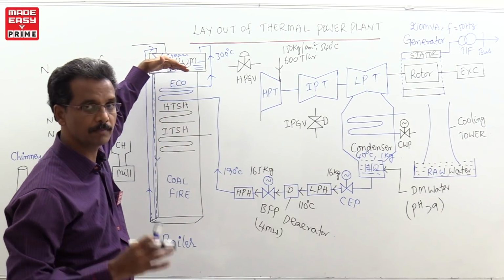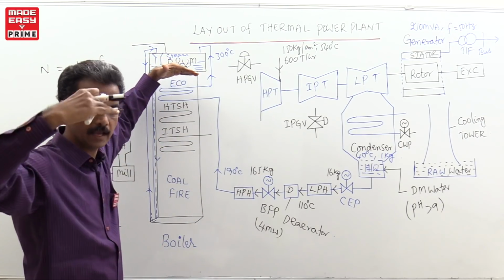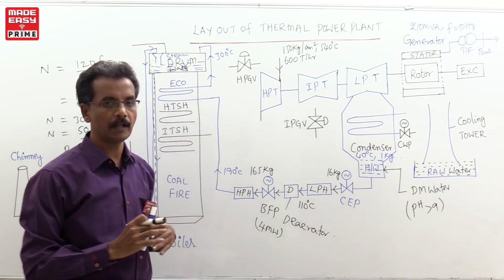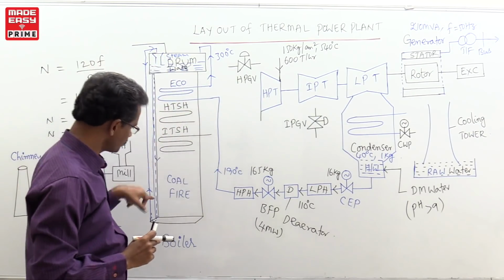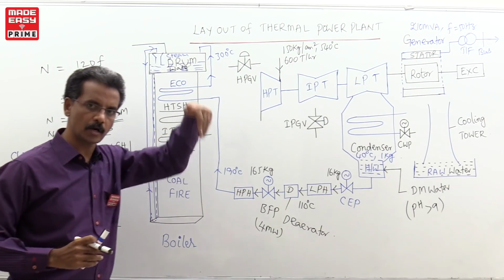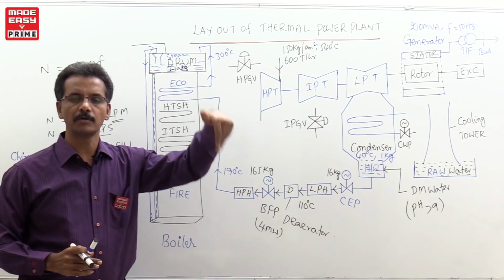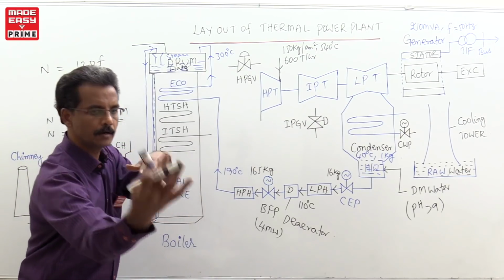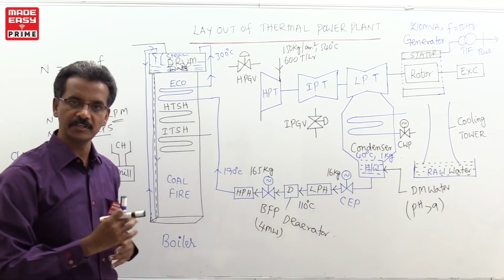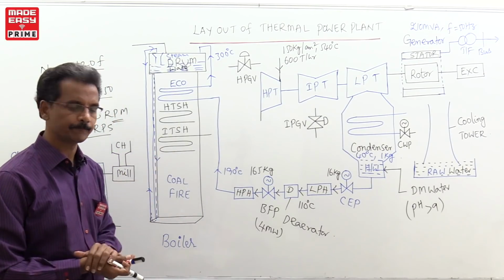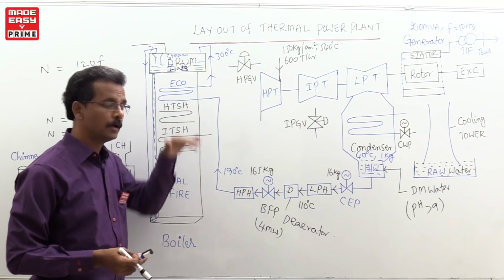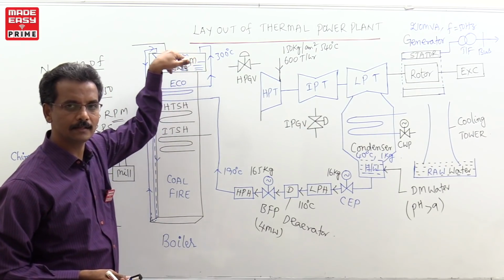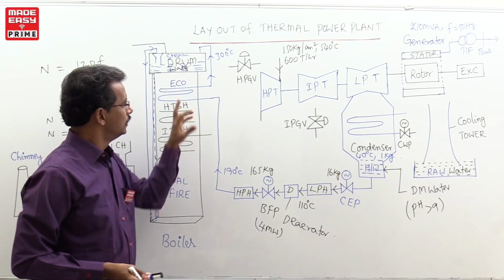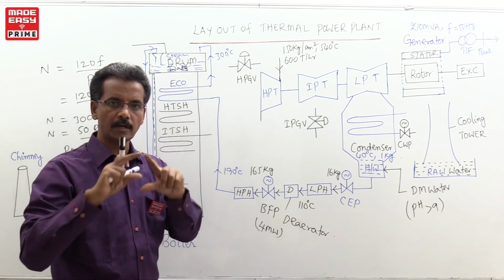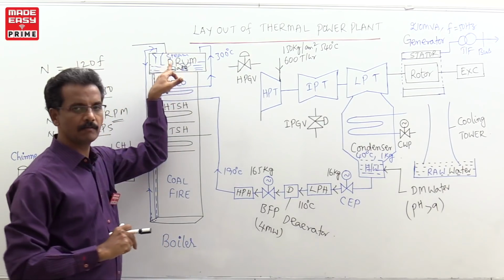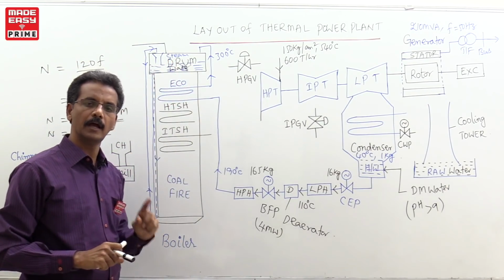Drum level is high means water level is high, and a high water level spoils the turbine. If the water level is low, what will happen? There is not a sufficient amount of cooling medium, that is, water is not flowing inside the tubes. If sufficient water is not flowing but the coal is already burnt and the tubes are gaining the energy, the tubes get damaged. This is the main drawback when the water level in the drum is low. That is why you have to maintain the water and steam levels at 50% and 50%.